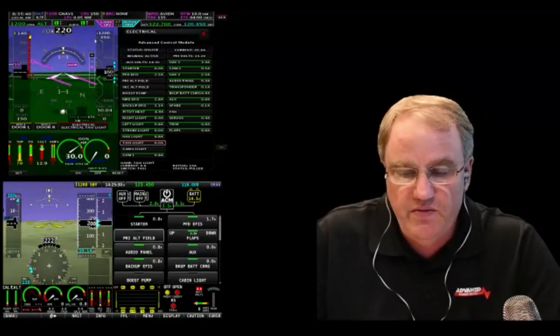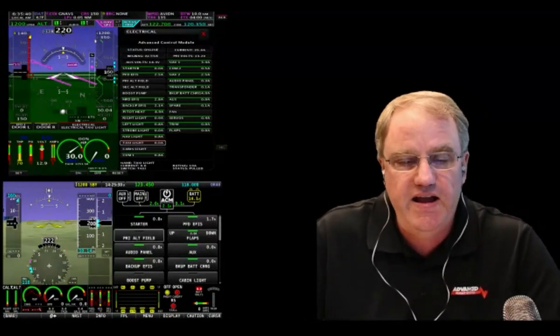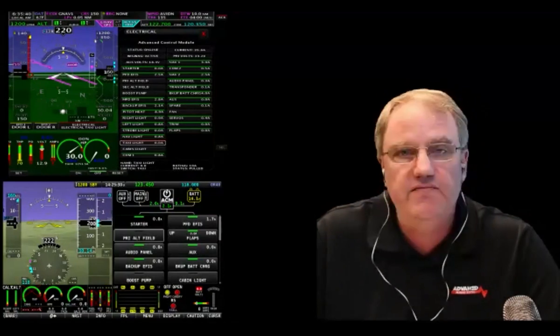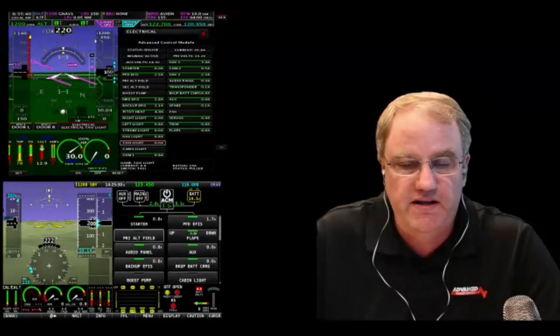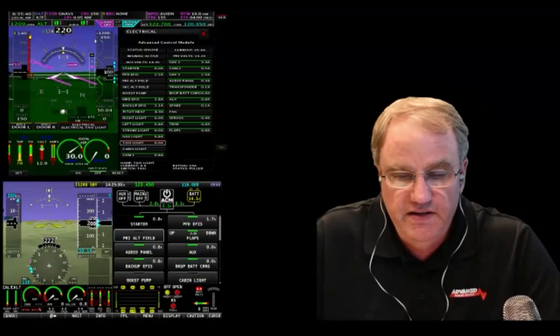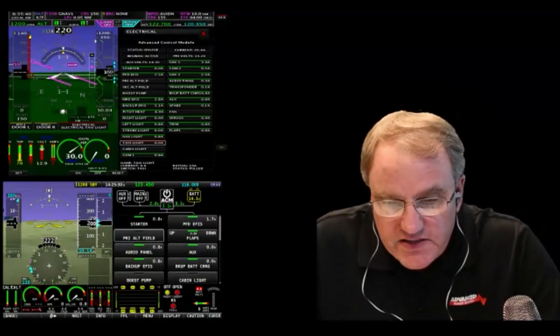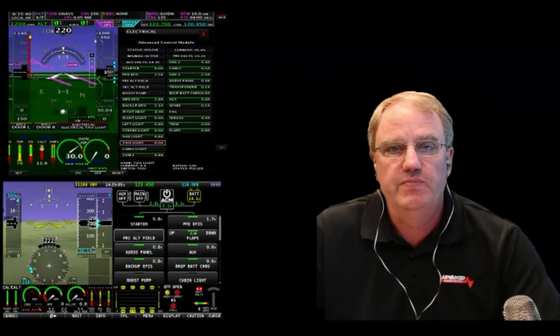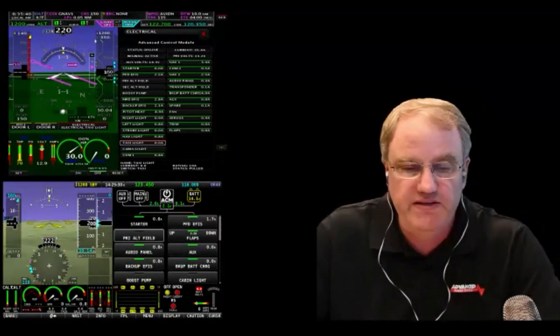The other advantage is you can actually see the amperage going to each device, so you can tell if a light bulb's burned out or something's not working without having to look. In this case, you can see the right landing light is drawing 0.9 amps. If the bulb was burned out or a wire was broken, it would be zero. So it gives you a lot of information on each circuit.